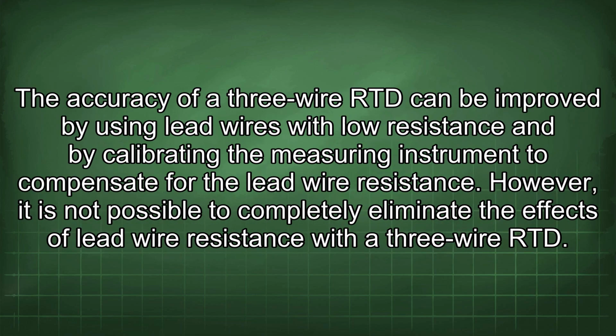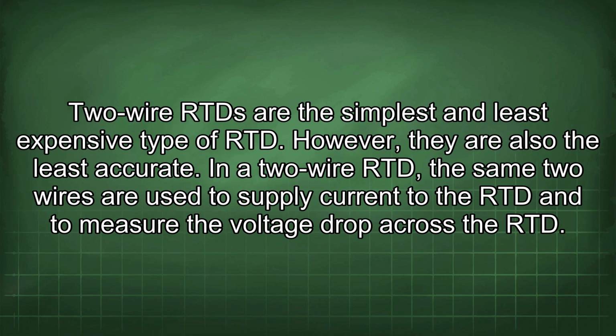The accuracy of a 3-wire RTD can be improved by using lead wires with low resistance and by calibrating the measuring instrument to compensate for the lead wire resistance. However, it is not possible to completely eliminate the effects of lead wire resistance with a 3-wire RTD. 2-wire RTD are the simplest and least expensive type of RTD. However, they are also the least accurate.